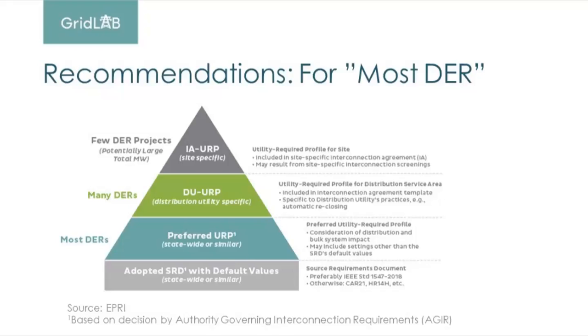Those are the standard settings for ride-through, as well as recommended settings for voltage regulation. And most DERs are going to be able to adopt those because most DERs are small. Maybe they go through the interconnection process, they get fast-tracked, there's no impact, and they're on a feeder with no other DERs.